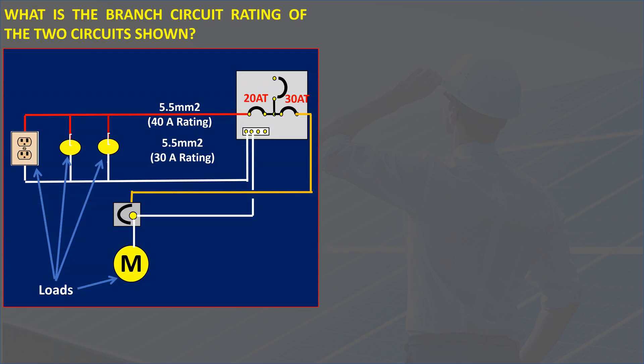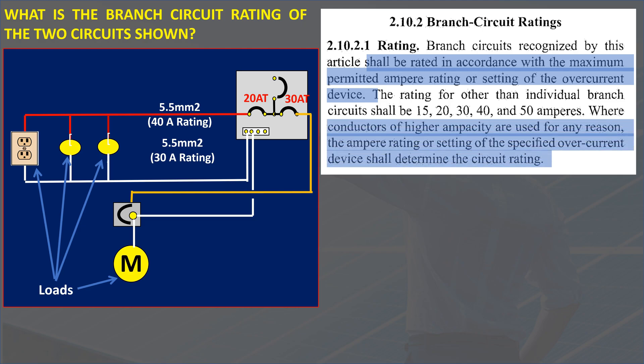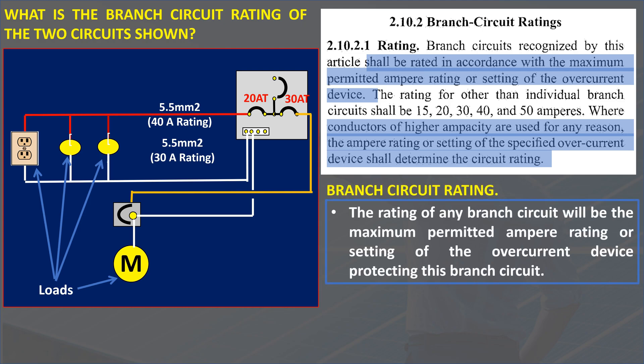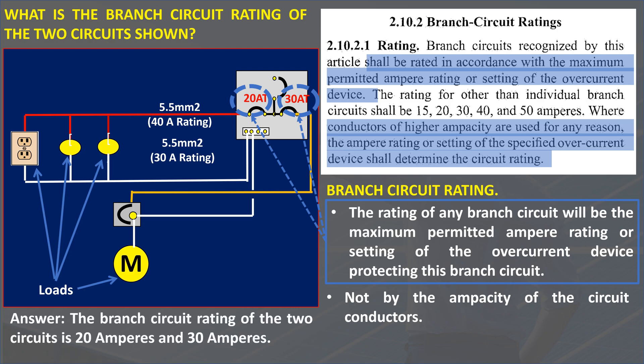What is the branch circuit rating of the two circuits shown? To determine the branch circuit rating, as per Section 2.10.2, branch circuits recognized by this article shall be rated in accordance with the maximum permitted ampere rating or setting of the overcurrent device. The rating for other than individual branch circuits shall be 15, 20, 30, 40, and 50 amperes. Where conductors of higher ampacity are used for any reason, the ampere rating or setting of the specified overcurrent device shall determine the circuit rating. Therefore, the rating of any branch circuit will be the maximum permitted ampere rating or setting of the overcurrent device protecting the branch circuit — not by the ampacity of the circuit conductors. The branch circuit rating of the two circuits is 20 amperes and 30 amperes.